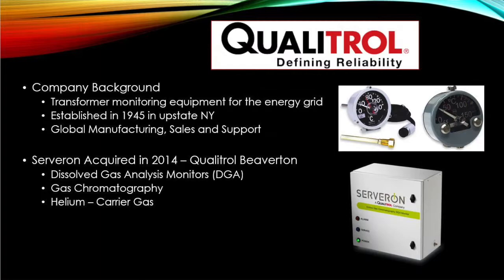Serveron builds dissolved gas analysis monitors, also known as DGA monitors. The Serveron dissolved gas analysis monitor uses gas chromatography, which requires a carrier gas to be used, and the carrier gas that is used is helium.